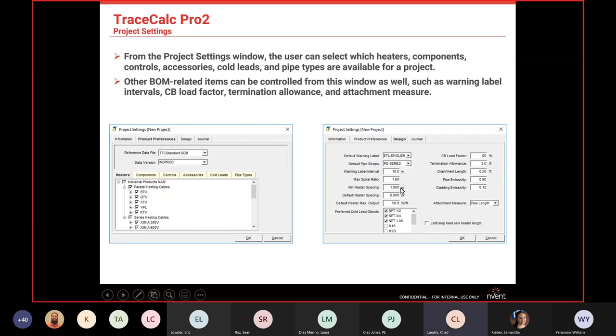Under Design Parameters, most values are defaulted. Some are for ETL labels — the labels you put on the pipe to identify that a line is electrically traced. We typically set those at 10 feet. Spiraling is available if you're spiraling cable around a pipe at a non-one-to-one ratio, but we don't practice spiraling because it's not construction-friendly or maintenance-friendly.